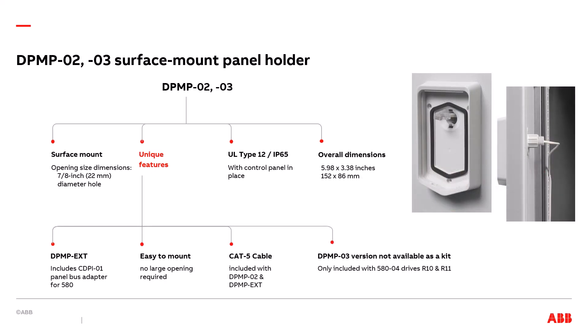The next type is the DPMP-02 and 03 surface mounted panel holder. The main benefit is the ease of installation and the small dimensions. This is a surface mounted panel holder, meaning the back of the panel holder is on the surface of the cabinet. This requires a smaller opening — only a 7/8-inch diameter hole is required. It has type 12 IP65 integrity. The overall dimensions are 5.98 inches high by 3.38 inches wide. A unique feature includes the availability of the DPMP-EXT version, which includes the CDPI-01 panel bus adapter for the 580 drives. The DPMP-03 version is not available as a standalone kit; it is included with the 580-04, R10, and R11 drives.